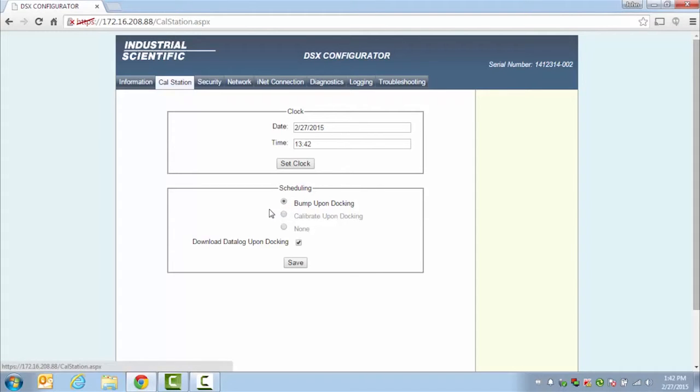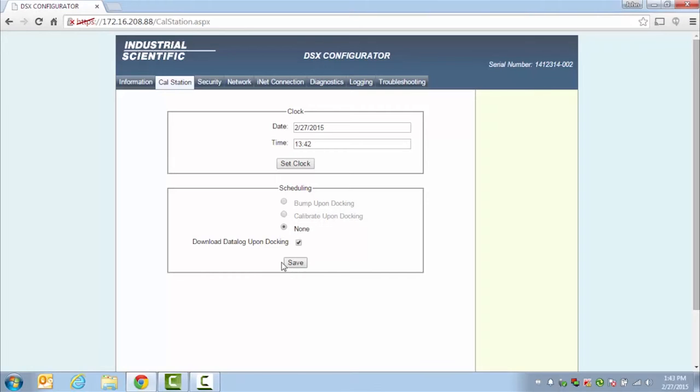By default, it is set to bump any instrument that is docked into it. You can change that to calibrate upon docking or to none, and then you will be required to choose between doing a calibration and a bump test every time via the DSX buttons.